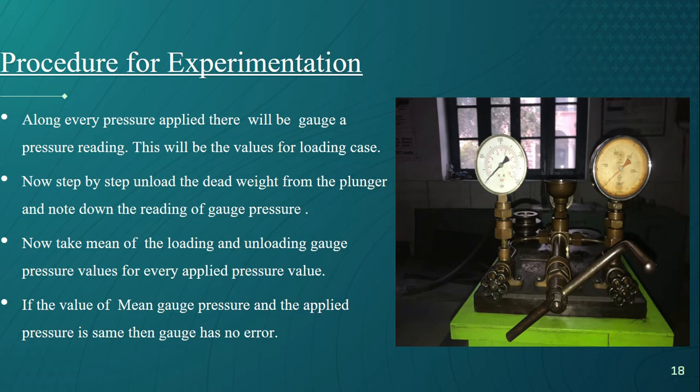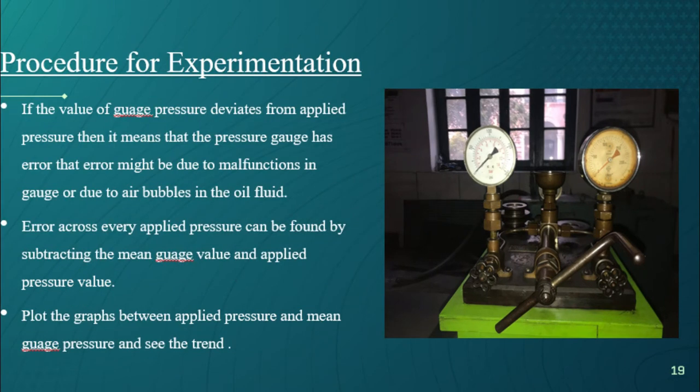Now step by step unload the dead weight from the plunger and note down the reading of gauge pressure. Now take mean of the loading and unloading gauge pressure values for every applied pressure value. If the value of mean gauge pressure and the applied pressure is same, then gauge has no error.